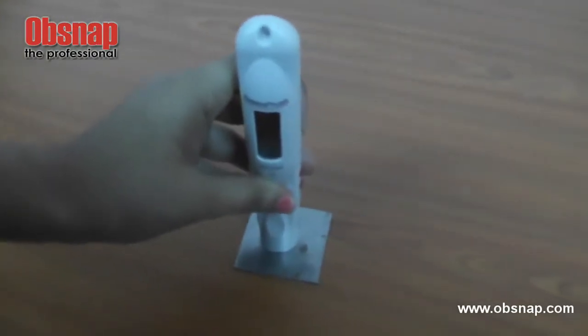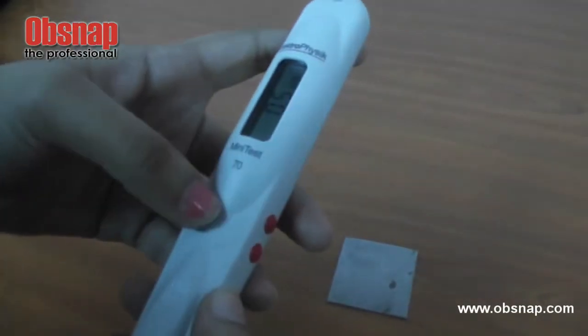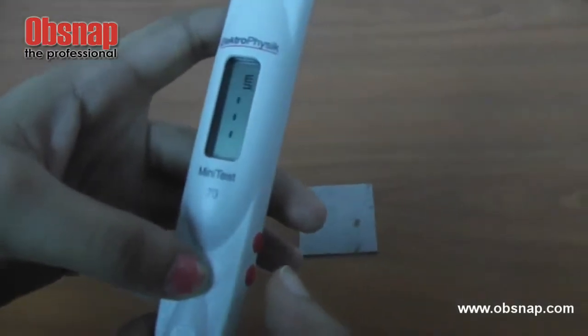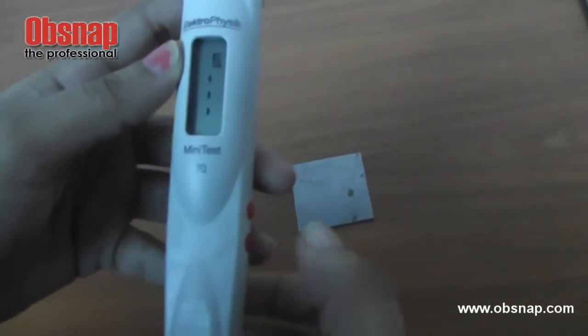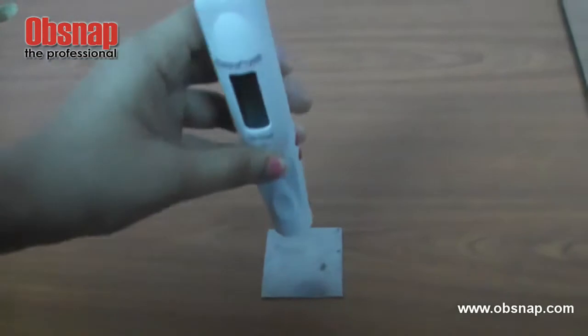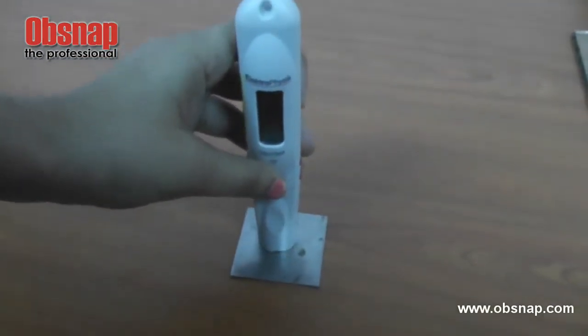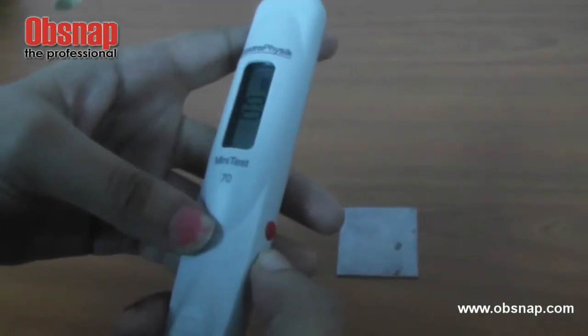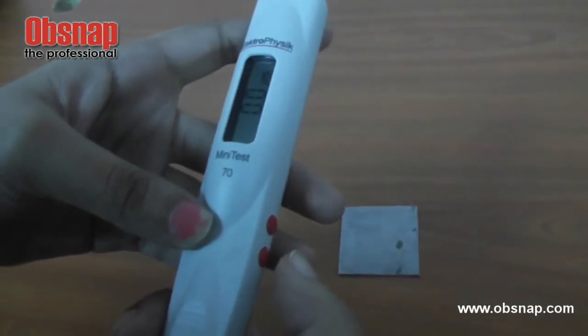So if the reading is not accurate, you can perform zero check or zero calibration by pressing on this on or zero button, and then you can see a flash on the display screen. Now you can place the sensor on the substrate, perform the zero check, and then press the zero button again. So, done testing the zero check.